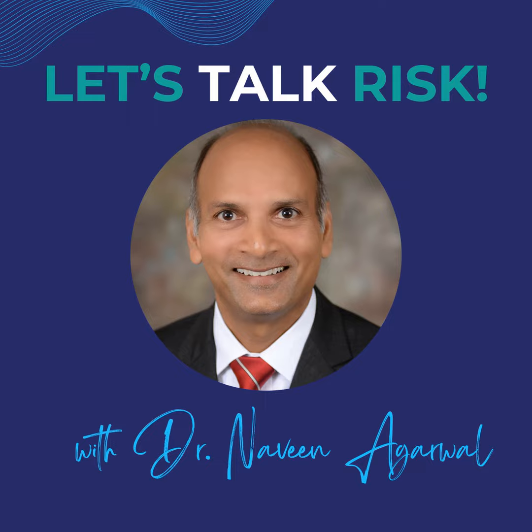The second mistake comes in missing the part of 7.3.4 in ISO 13485 that requires design outputs, that is specifications, to include acceptance criteria. Tough to do the second without doing the first correctly and fully.